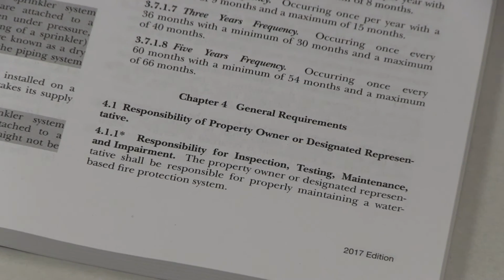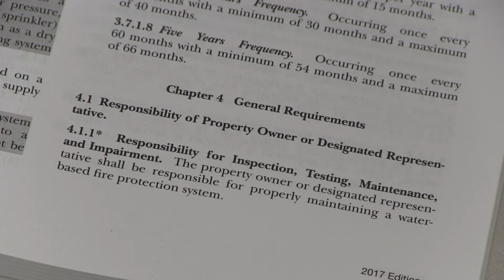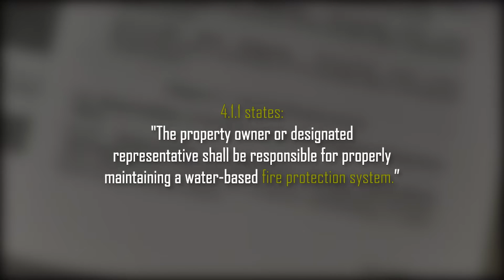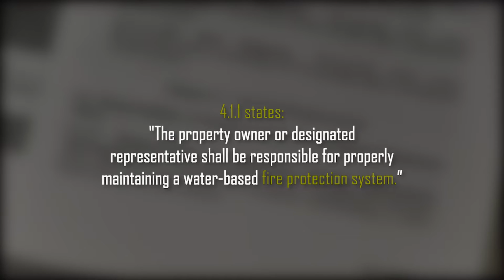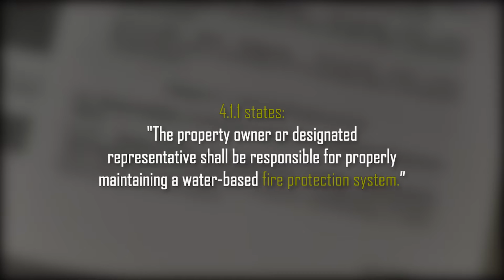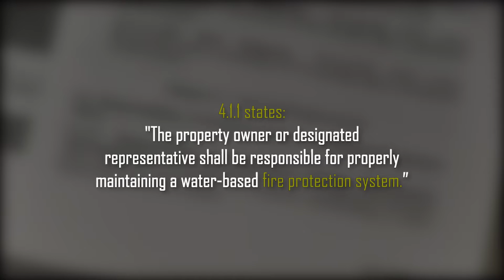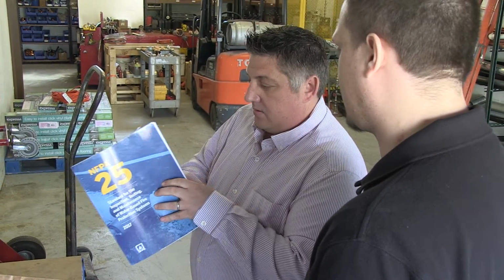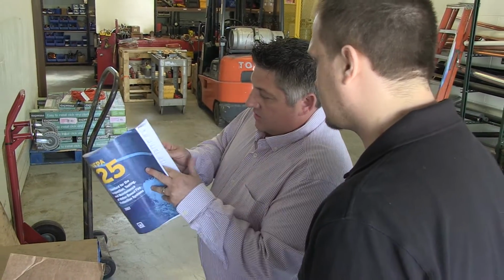As a building owner or manager, the bulk of your responsibilities are listed within Chapter 4.1 of NFPA 25. Just as you would refer to your car owner's manual for car maintenance, you refer to Chapter 4.1 for fire sprinkler system ITM. Chapter 4.1 states that you, the building owner or manager, are responsible for the ITM of your building's water-based fire protection systems. If you are not the occupant of the building, you may choose a designated representative in the building for the management of ITM. He or she will be held to the same requirements as the building owner or manager.